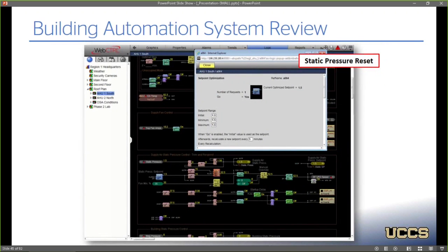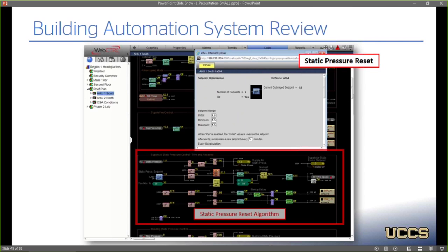The static pressure reset, I had mentioned that the algorithm was in place, which is this block diagram here. So it's there, and it's trying to do what it was programmed to do, but the minimum and maximum set points are set to 1.5 inches, so it's not actually able to do anything with it.